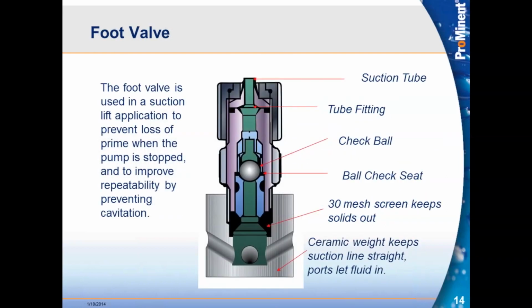The weighted foot valve we talked about, it's an additional check valve, so you do see the ball check seat there, the check ball. The seat is below the valve ball, of course, allowing the flow to go up through but not come back down. So once we've lifted that fluid, we don't have to lift it again. It's going to continue to progress up towards the pump. At the top, you see the tube fitting. That thread at the top, remember, is going to be metric, but that doesn't matter because with our tube fitting, our compression fitting, or our connector set as we typically describe it, that's what's important for handling the dimensions of the tubing. And we can always handle standard size tubings that we find here in the States. So that's not a problem.